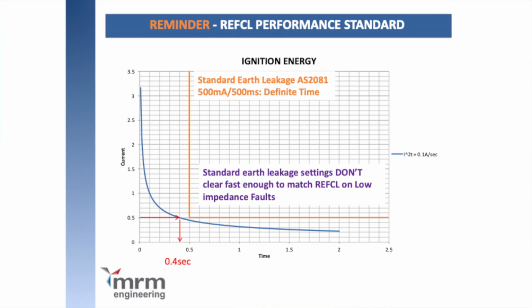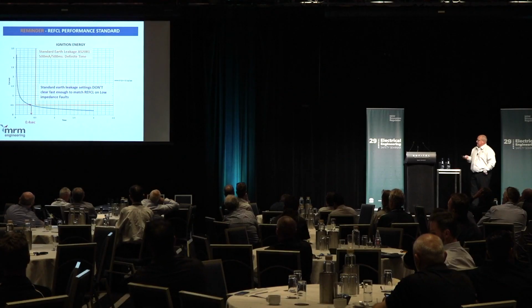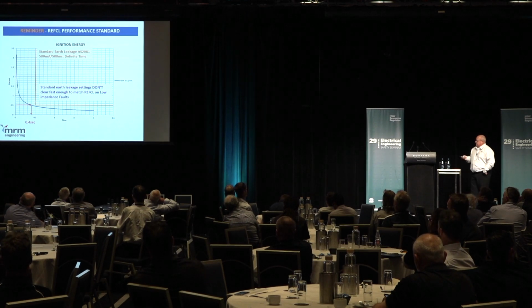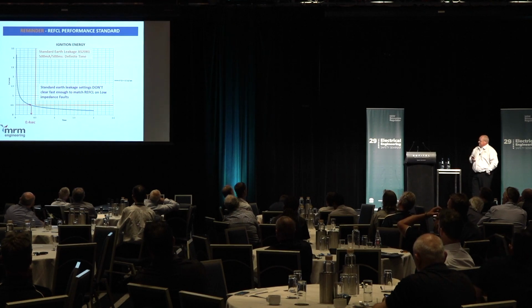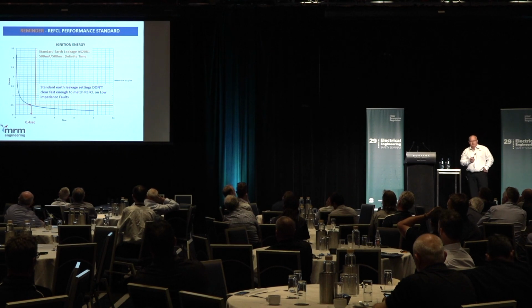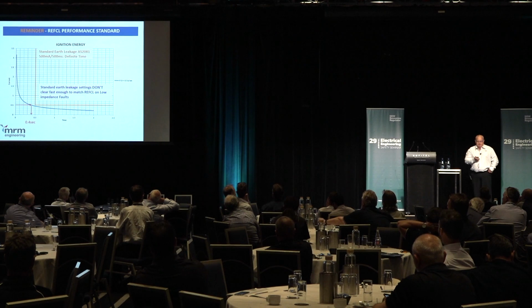So this graph again is back to the ignition energy. So when we compare our stated currents for 500 milliamps, 500 milliseconds from 2081, right? We're here in that orange curve, and the blue curve is below that. So their protection is probably going to operate a lot quicker than what we can detect. So any fault in our system, we probably won't detect, and will be blocked by their system.